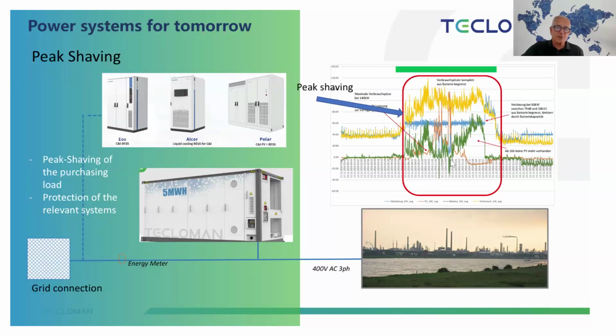For peak shaving opportunities, you can also use small capacity storage systems up to 200, 400, 600 kilowatt hours, up to 1 or 2 megawatt hours, or containerized solutions like you see here - 5 megawatt hours in a 20 foot container can also help you achieve these peak shaving opportunities.